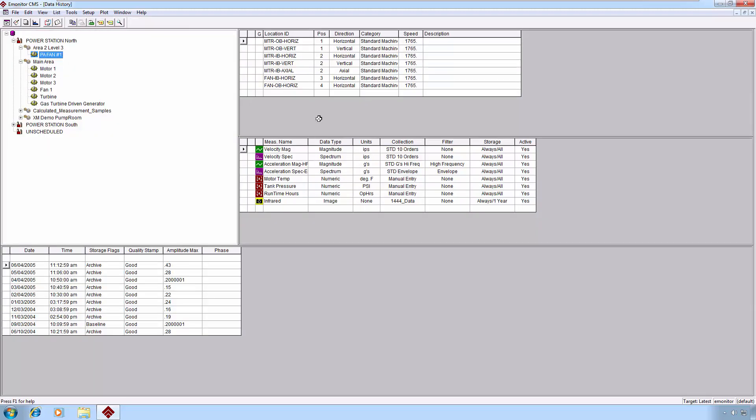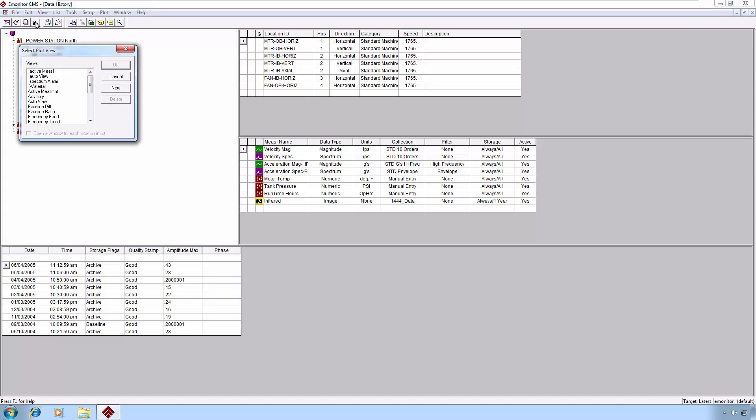Another way to compare two spectrum plots, for example, would be if you wanted to, say, compare the current spectrum to the baseline. You could, as I mentioned, overlay those plots by tagging them and then looking at the spectrum and then choosing to overlay that data. But there's actually a better view for that that makes that a little bit more easy to interpret what's going on, and that's called the baseline differential. Notice there's a baseline ratio, which simply divides the two spectra from each other. The differential subtracts them, as you'll see.